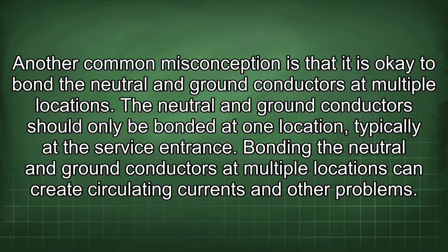Another common misconception is that it is okay to bond the neutral and ground conductors at multiple locations. The neutral and ground conductors should only be bonded at one location, typically at the service entrance. Bonding the neutral and ground conductors at multiple locations can create circulating currents and other problems.